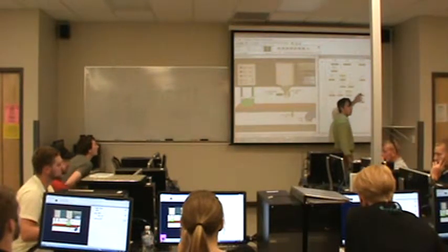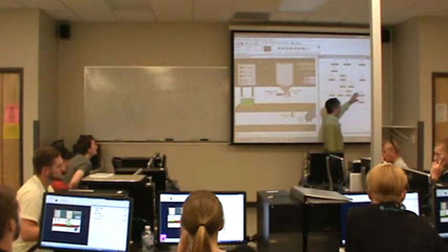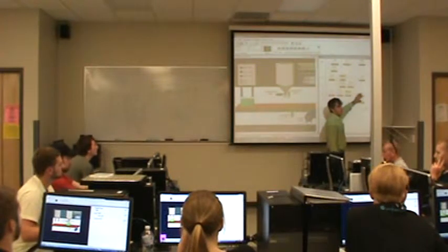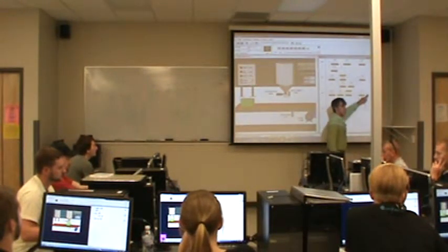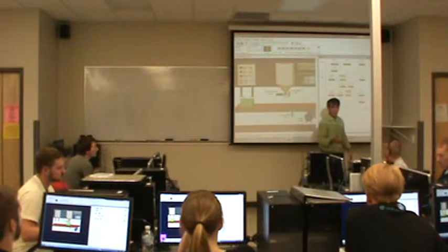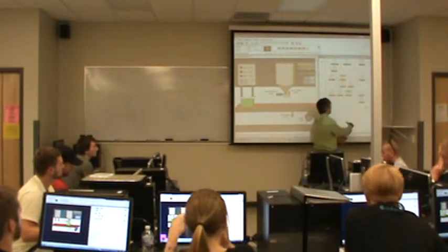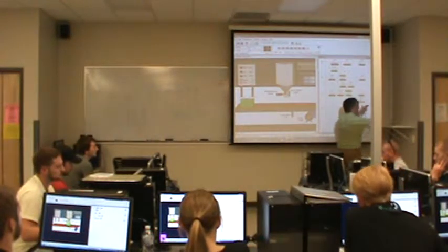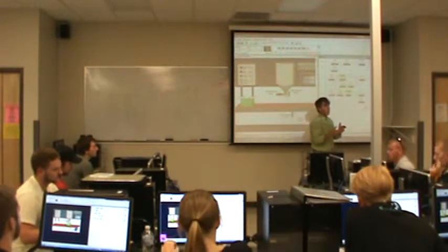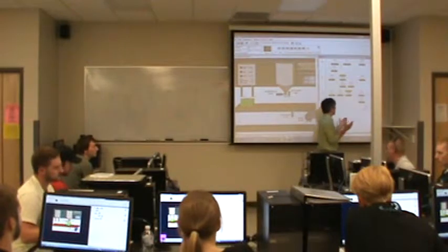This is the way I prefer you to set it up. If you're going to have two outputs on a single rung, I prefer that you set it up this way. You could set them up in series, one after another, but if an electrician looks at this as if it's a schematic, he's going to go, what the heck is this? Because you've got half the voltage drop across one of the outputs, and the other half across the other one. That makes no sense to you, okay, or her.